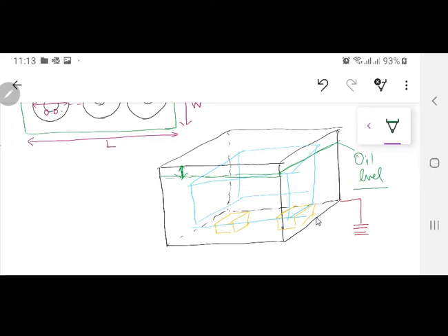If the level of the oil goes down to a threshold value, it triggers an alarm and also isolates the supply from the transformer, because if the transformer has no oil, it can't dissipate the heat. If it can't dissipate the heat and you turn it on even for 15 minutes to an hour, it will short circuit itself or heat up and destroy itself.